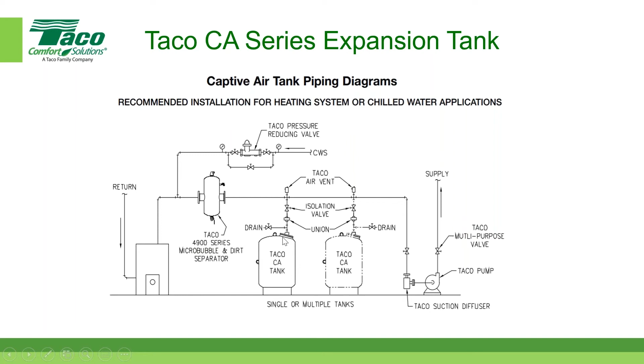So an ASME vessel has to have documentation forever associated with it. That gets you all that information as well. Here's a recommended old style drawing. There's the suction to the pump. I'm showing an option of 2 or 1, and some people pipe them in parallel or together. We can have a discussion about that. But there's that isolation valve, and good piping practice, a union in there so you can separate it without having to cut the pipe or anything. And there's that drain fitting there.